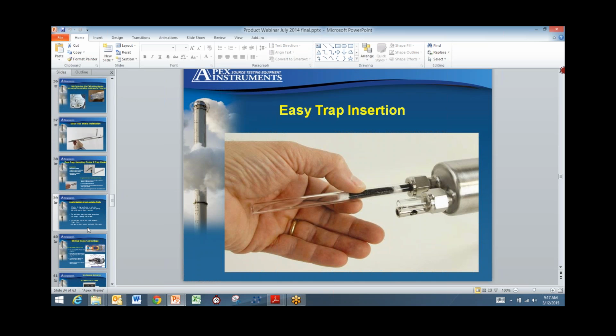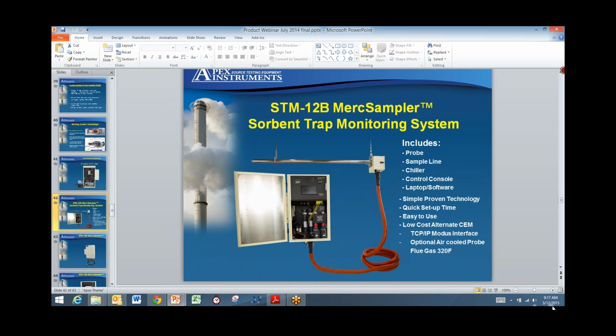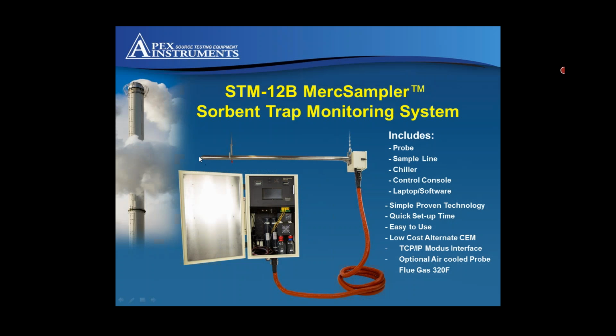So once we insert that into the stack, what we're going to be looking at is basically pulling the sample through the probe. We will have a heater here in the probe, and it'll run down to about here, the first heater. What that'll do is make sure we keep that sample above the dew point, so we're not getting any moisture in the sample, whether in the trap or coming down the probe, because that can affect our results. So we'll keep that sample nice and hot.